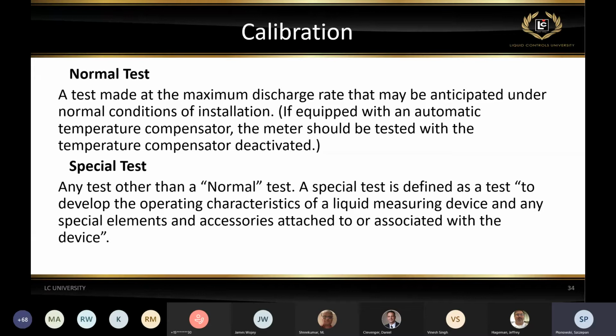So let's say the meter is an M7 and it's rated for 100 gallons. That meter will often be used close to that flow rate, maybe at 70, maybe 80 gallons. So you would be calibrating and checking the accuracy of that meter at that flow rate. Generally, normal testing is done with temperature compensation turned off, either mechanical or electronic. With mechanical compensation turned off, all the normal testing is done in gross mode.